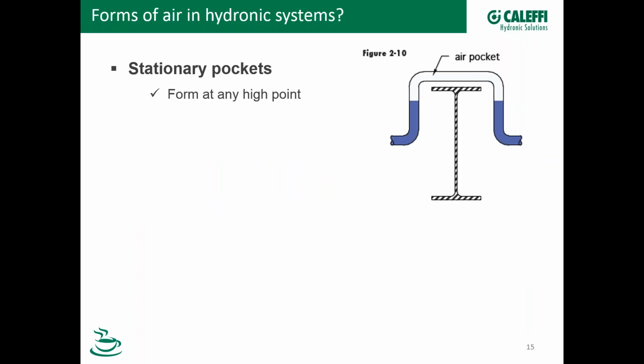All right, so let's look at some forms of air in hydronic systems. A stationary pocket, the first thing we're going to talk about is an air pocket. Now this is going to form at any high point in the system. Here's an example of an air pocket that's on a high section of pipe. So you can find these high sections in heat emitters, heat exchangers, expansion tanks, whatever. You can form these bubbles, and as they join together, they'll form these large high pockets, okay?